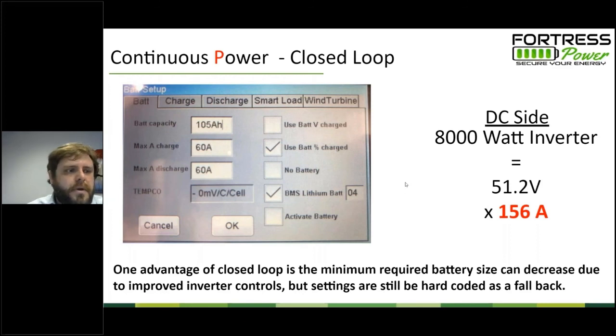On Bill's question, since it's on topic: why does it matter if the max inverter input spec is higher than the battery discharge spec? Isn't the battery going to discharge based on the load, not on the inverter max input spec? The answer is yes. But what an inspector is going to look at is, if this inverter does run continuously at its rated maximum output, is the system designed within spec?